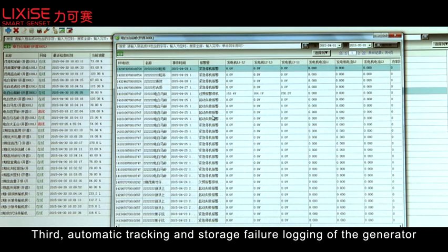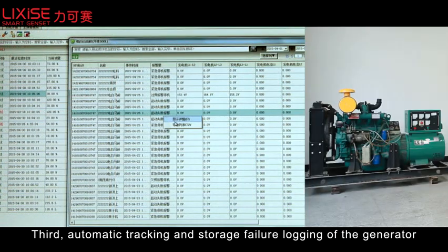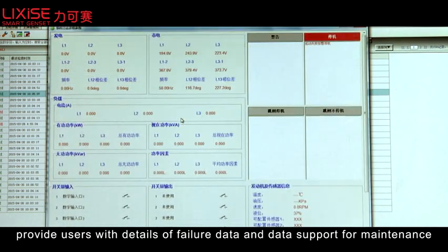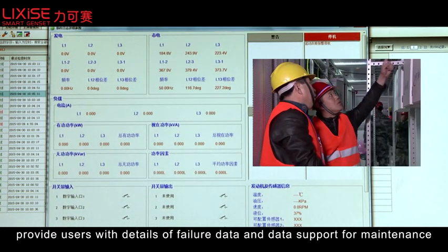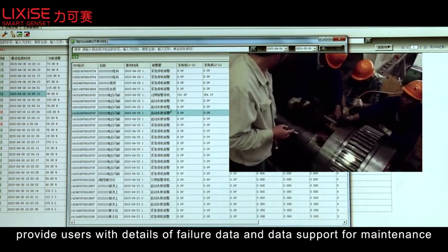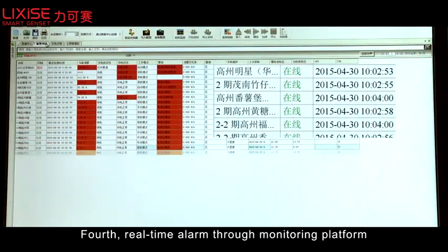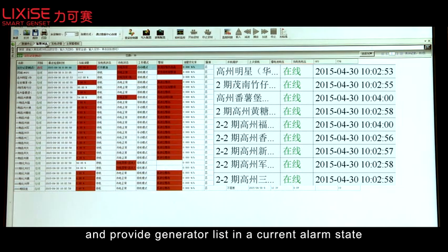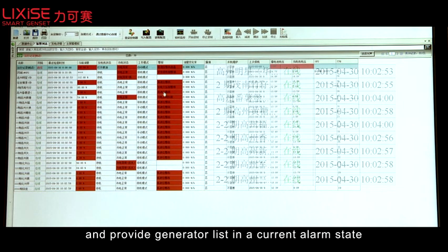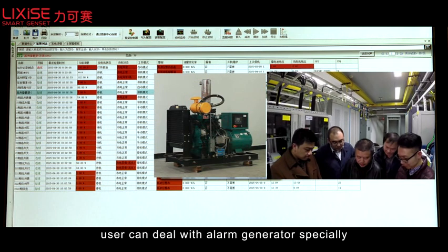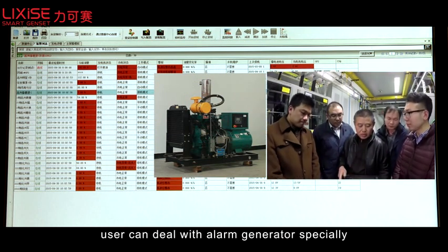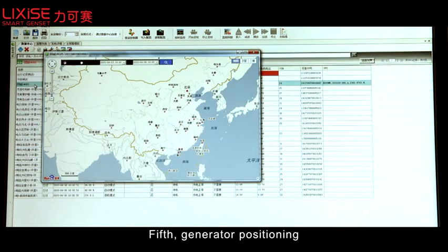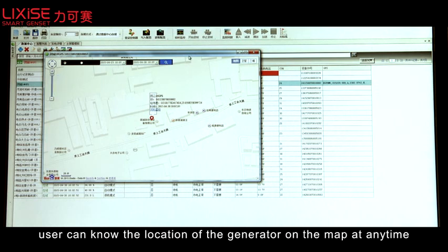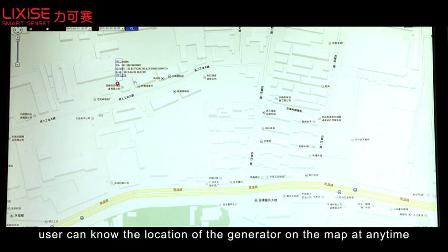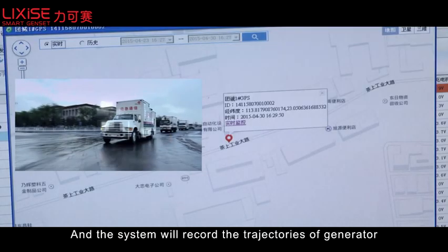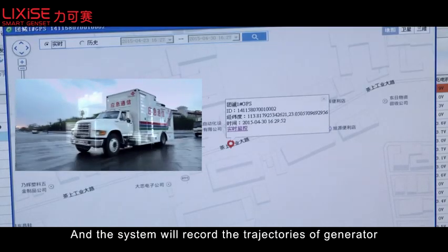Third, automatic tracking and storage failure logging of the generator provide users with details of failure data and data support for maintenance. Fourth, real-time alarm through monitoring platform and provide generator list in a current alarm state. User can deal with alarm generator specially. Fifth, generator positioning. User can know the location of the generator on the map at any time, and the system will record the trajectories of generator.